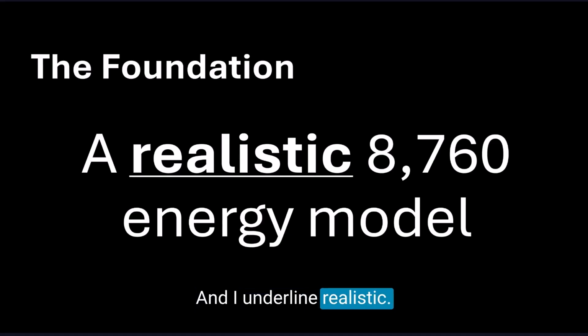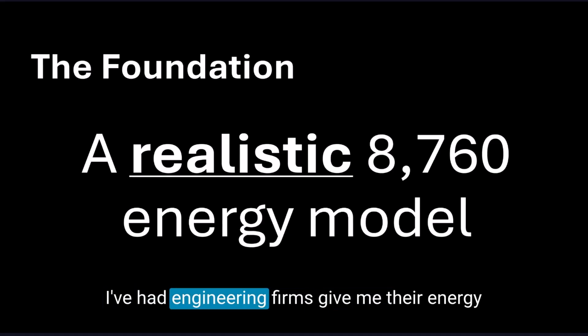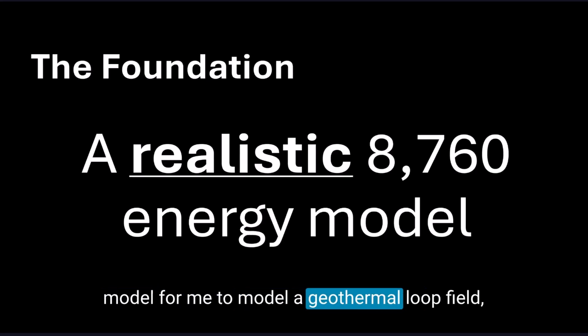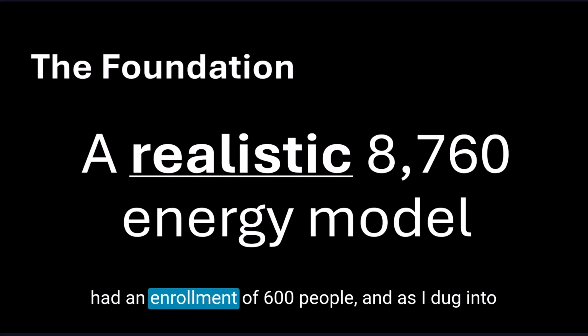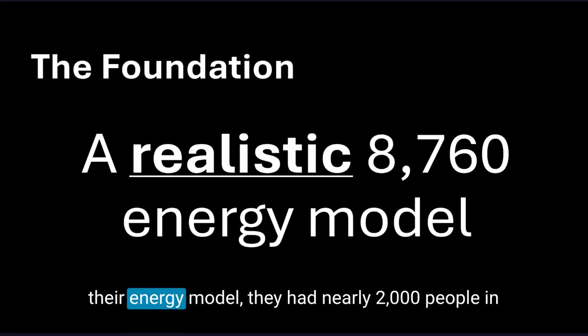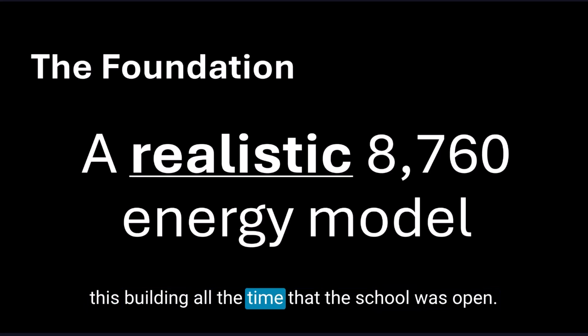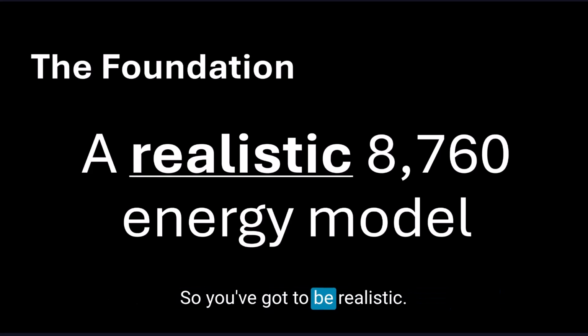And I underline realistic. I've had engineering firms give me their energy model for me to model a geothermal loop field. And one example was a modest-sized school. They had an enrollment of 600 people. And as I dug into their energy model, they had nearly 2,000 people in this building all the time that the school was open. So you've got to be realistic.